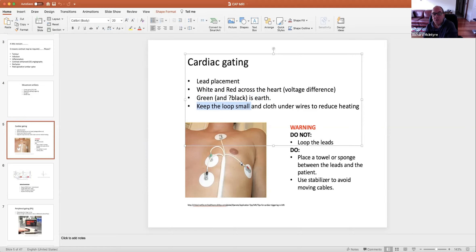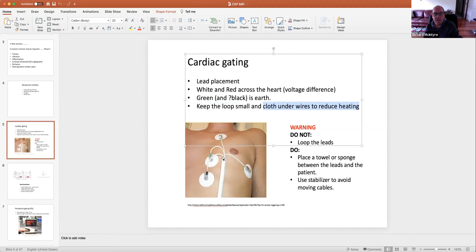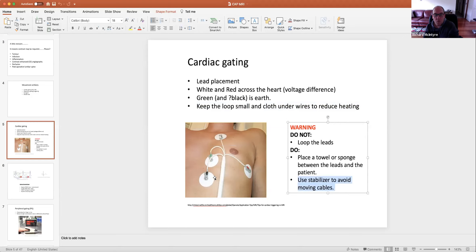If we have no current and we're not changing the magnetic field, we won't get an extra signal between those two loops. Whereas if we do change the field, we're going to generate a signal here that detracts from the actual heart signal. We also want to keep a cloth under the wires to reduce heating — if they do heat up, they're not directly onto the skin. A stabiliser is important too; if we move those wires, we're going to generate a signal.